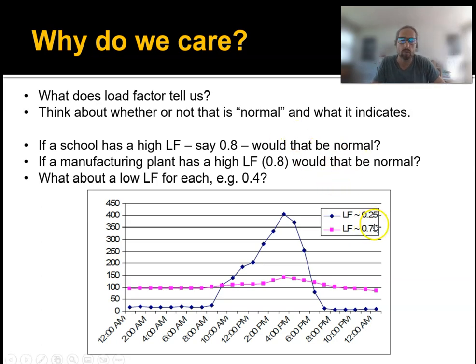And that's abnormal, and if you go back to what we were talking about before, that means the peak demand is probably higher than it needs to be, and so there may be an opportunity for energy and money savings if they're paying for demand, right? So they're having this unusually high peak demand, and that could indicate that there's an opportunity for energy savings.